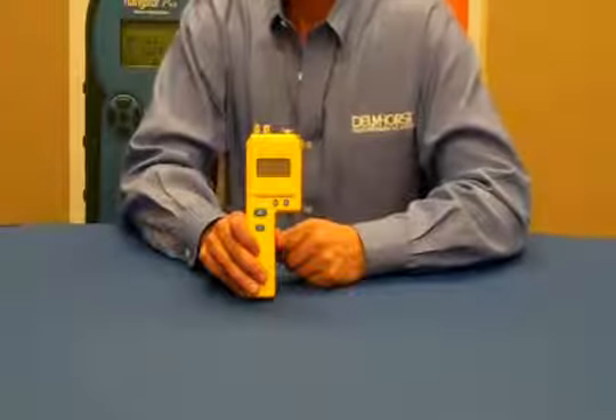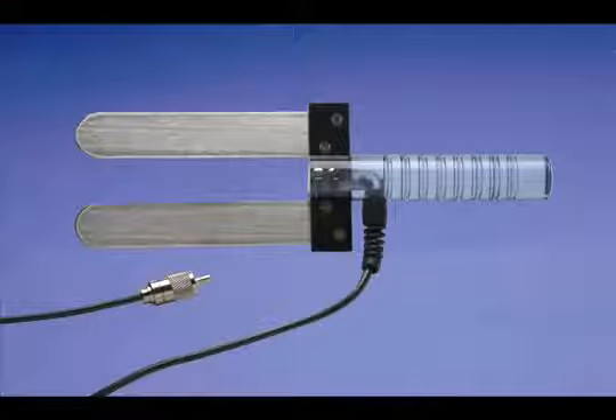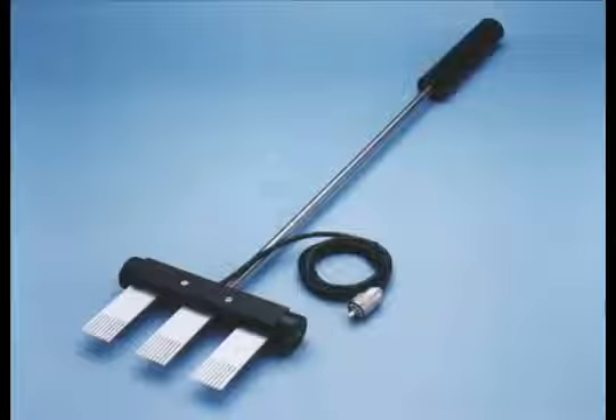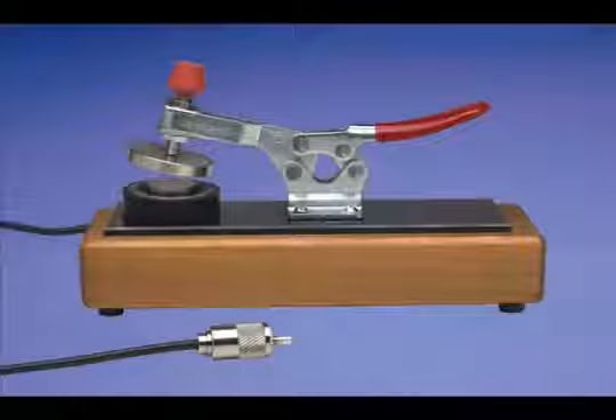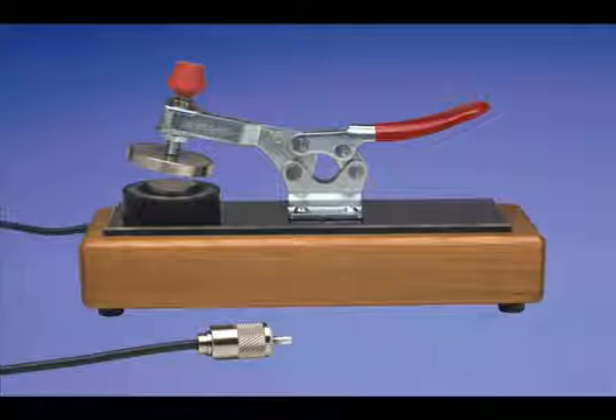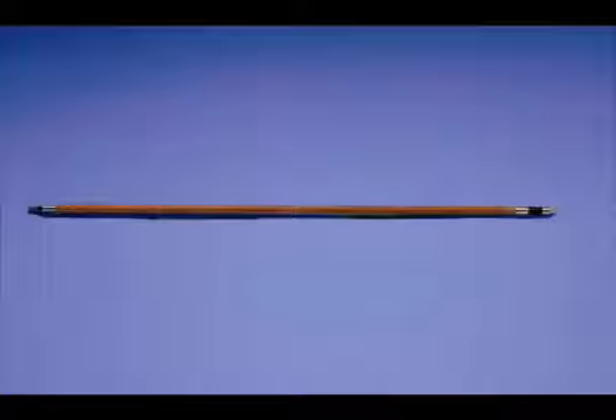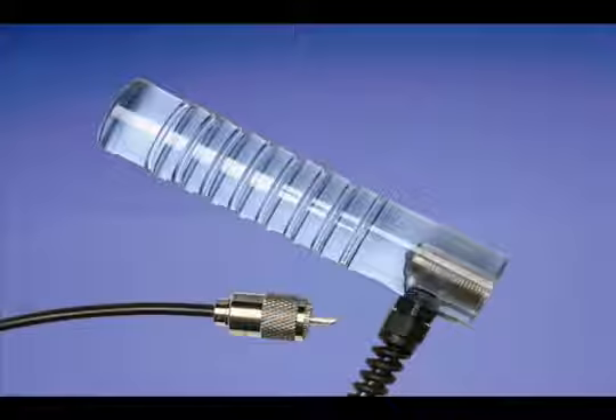The most popular electrodes for paper are the 19E for paper on skids, the 12E or the 55E for paper on a moving web or roll, the 43E for thin sheet stock, the 2E for cardboard tubes, and the 830-2 10-inch prod with H4 handle for baled scrap paper.